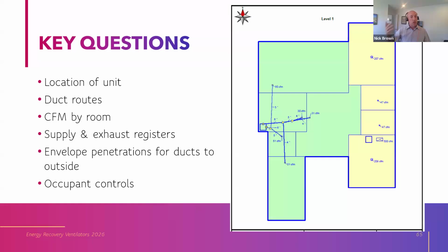So the key questions to think about as you consider this business or your own house: where does the unit go? What route will the ducts take? What CFM does each room need? Where will the supply and exhaust registers be located? And that penetration of the building envelope is a really important detail—how are you going to get fresh air in and exhaust stale air out?